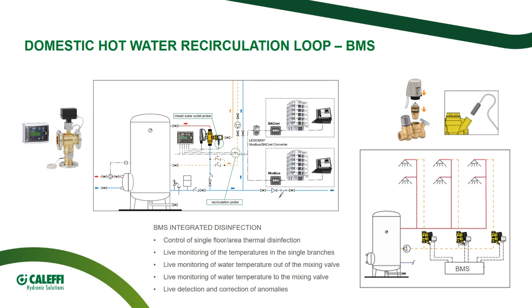So think about the hotel we discussed before. Okay, the mixing valve is operating the disinfection, but the top floor is not correctly balanced, and on that floor, the temperature is not reaching the correct set value. The Legionella on the tenth floor, the last floor, will still be alive even after the disinfection. So it will start again infecting the rest of the system. That's why monitoring the temperatures throughout the building is so important.